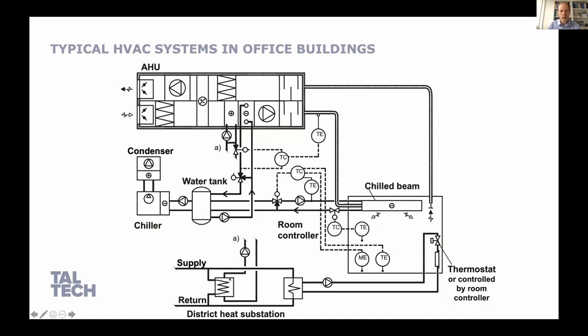Very typically, and also in this building, district heating has been used, with water radiators for heating as a very robust and effective system, while active chill beams provide ventilation and cooling to the rooms. The cooling source is typically outdoor air, so there are chillers combined with a free cooling option—these systems are most commonly used in office buildings.